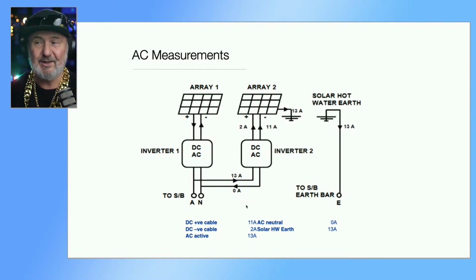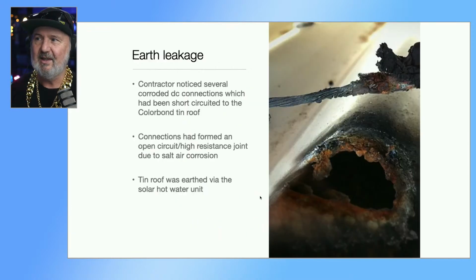Whoa, 24/7. What was the reason? So the brave technician got up onto the roof. I'm saying brave because this is very dangerous, and discovered that there were some big holes in the roof where the plug and sockets had blown the metal away from the corrugations. And it was in a rather close proximity to the ocean. Not quite sure how close, but salt spray or salt mist would have definitely been an issue. And they were concerned that it was probably due to salt-rich air causing some corrosion of those connecting parts.